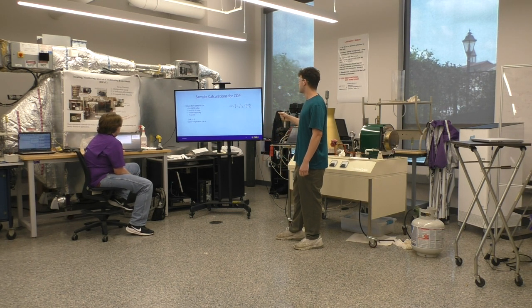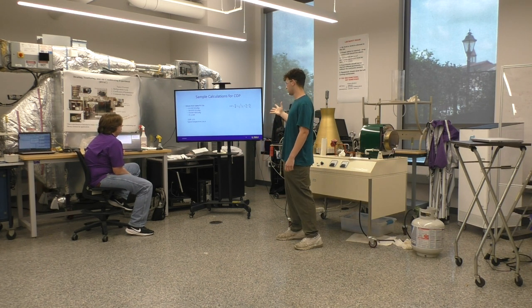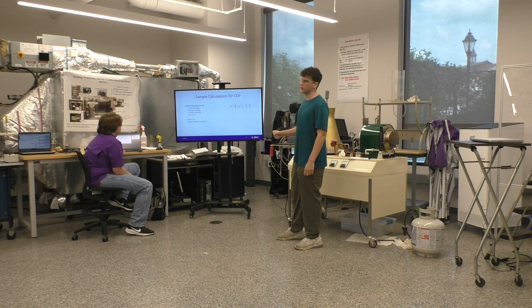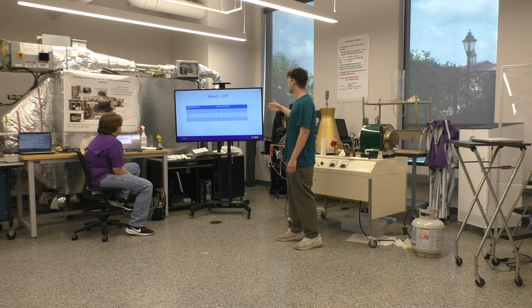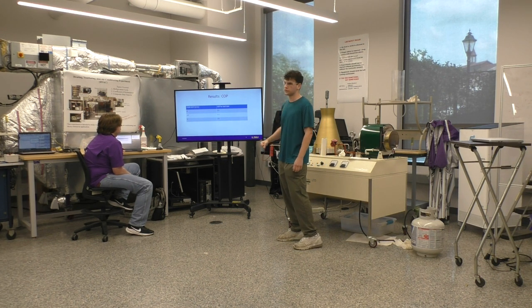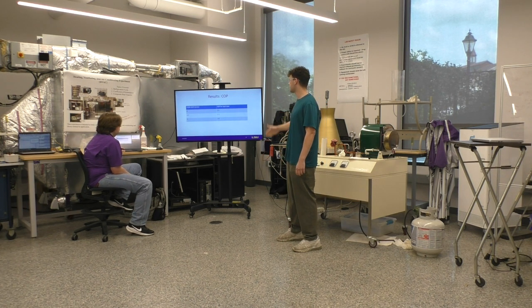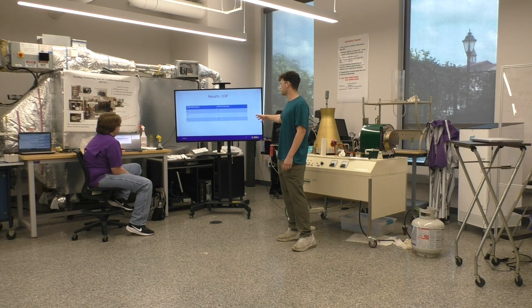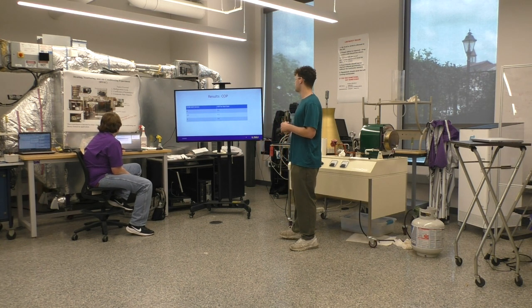And from that, this is for the 6 liters per minute test. We had a COP of 2.5, and it does, again, average from 2 to 4, so that is a reasonable outcome. Next, these are the COPs for the different tests. As you can see, the coefficient of performance of the refrigeration cycle reduced as the flow rate was reduced as well. This is similar to other data from other experiments.